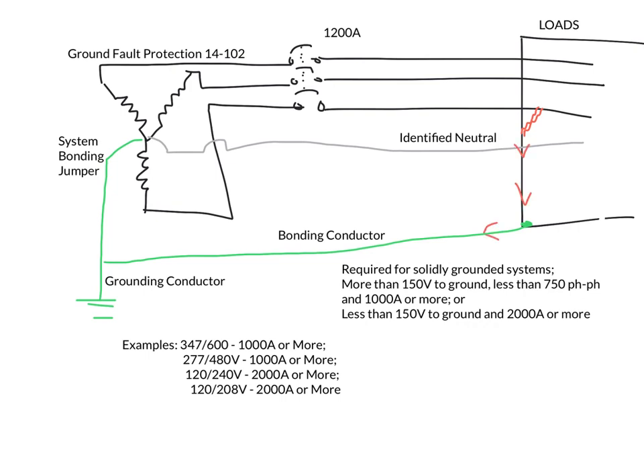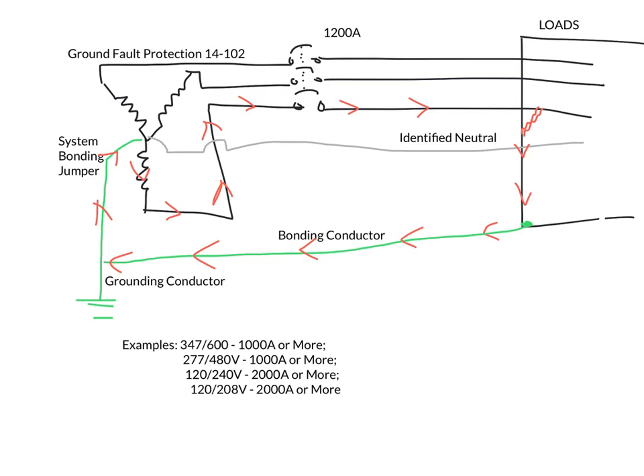Because as we recall, fault current is going to flow back on the bonding conductor. It's going to complete a path back through the transformer, through the faulted phase, and in an ideal world, this should open up the overcurrent device, but in these types of systems with these ratings, that doesn't always happen. So the code requires this thing called ground fault protection. It's a way of sensing that a fault exists on the system and opening up the circuit when the breaker or fuse may not open on its own. The key reason we want this type of protection is that if we allow this arcing fault to persist, it's going to pose a fire hazard. It's not necessarily a shock hazard because there is a dedicated path for fault current to flow, but it definitely can cause fires, and that's something we don't want any of our systems to have.